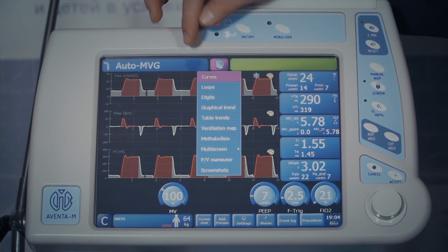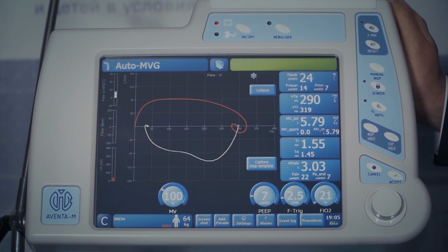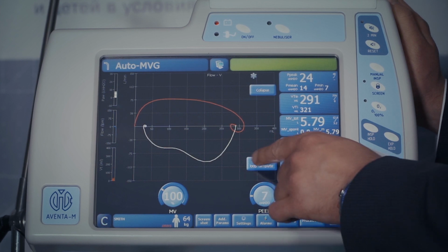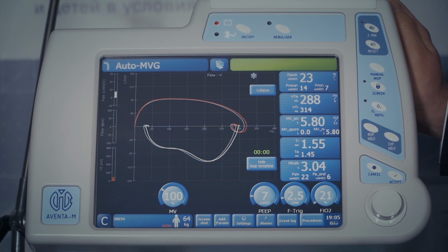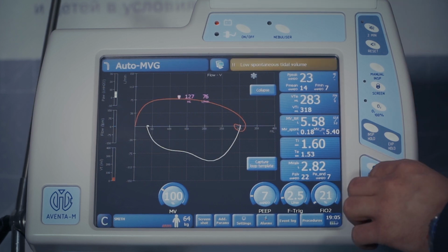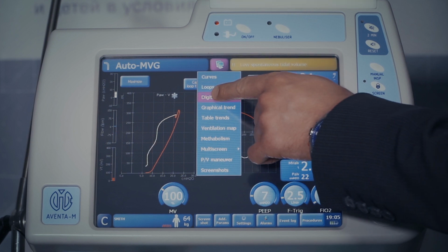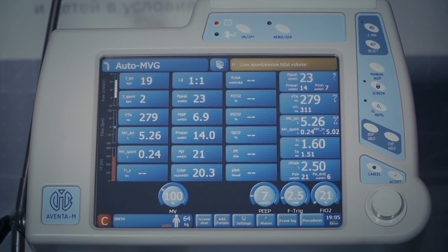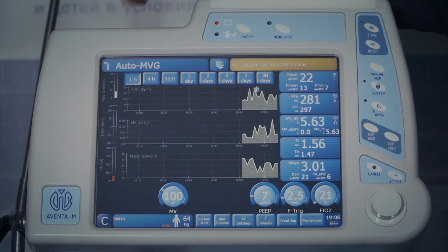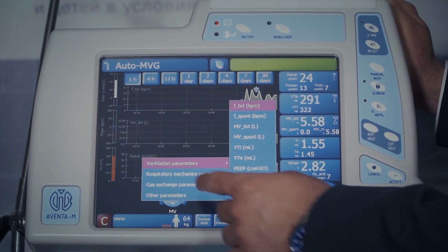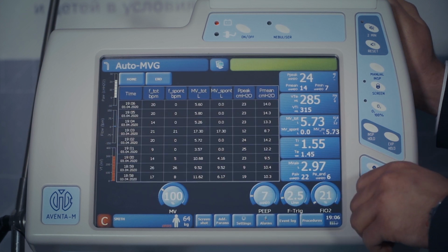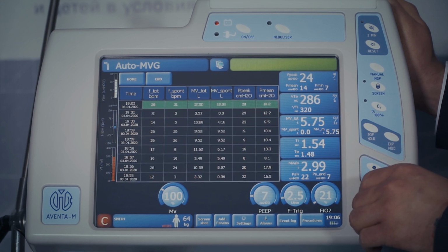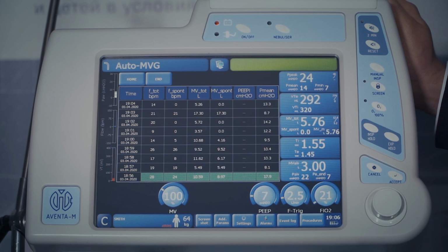It is also possible to change the breathing loop's colors, freeze them for detailed study. Set the current breathing loop as the reference one to compare the same with the following breathing cycles. Besides, it is possible to select numeric parameter window that allows to obtain the maximum information about the current ventilation parameters. Then, there are trend windows, graphic and tabular. Graphic trend window allows to select the information display time in the range from 1 hour to 30 days and adjust graphically displayed parameter. Tabular trends represent the same information but in numeric format.